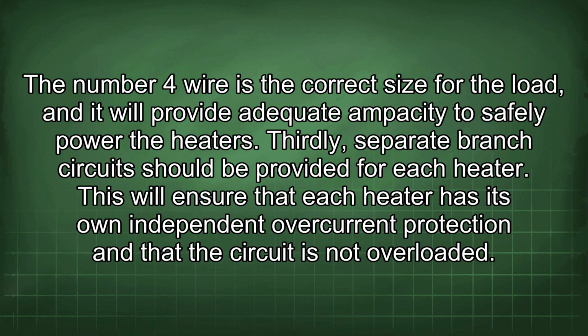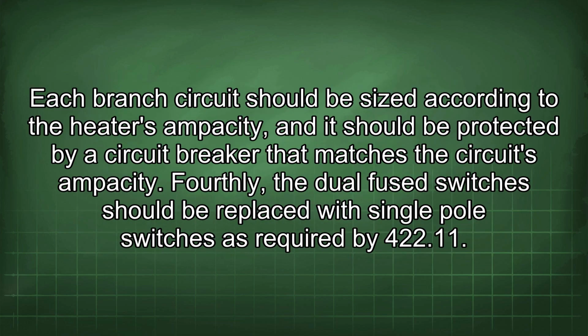Thirdly, separate branch circuits should be provided for each heater. This will ensure that each heater has its own independent overcurrent protection and that the circuit is not overloaded. Each branch circuit should be sized according to the heater's ampacity, and it should be protected by a circuit breaker that matches the circuit's ampacity.